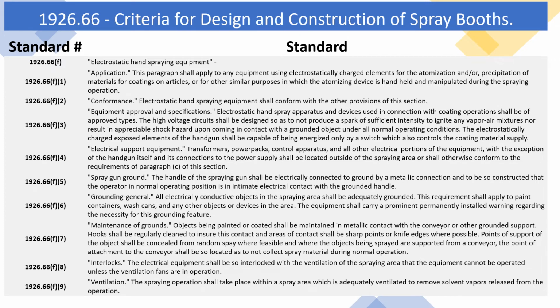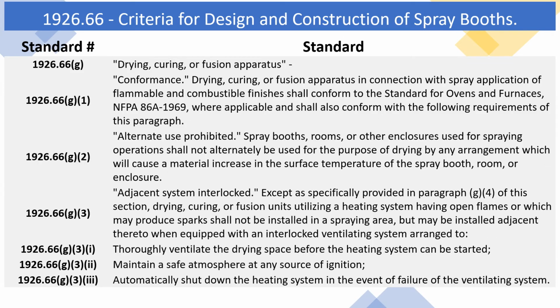1926.66 F8 Interlocks. The electrical equipment shall be so interlocked with the ventilation of the spraying area that the equipment cannot be operated unless the ventilation fans are in operation. 1926.66 F9 Ventilation. The spraying operation shall take place within a spray area which is adequately ventilated to remove solvent vapors released from the operation. 1926.66 G. Drying, curing, or fusion apparatus. 1926.66 G1 Conformance. Drying, curing, or fusion apparatus in connection with spray application of flammable and combustible finishes shall conform to the standard for ovens and furnaces, NFPA 86A 1969, where applicable, and shall also conform with the following requirements of this paragraph.